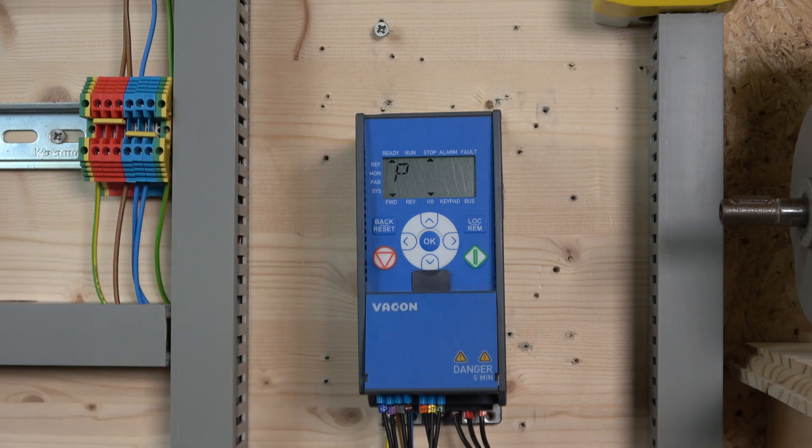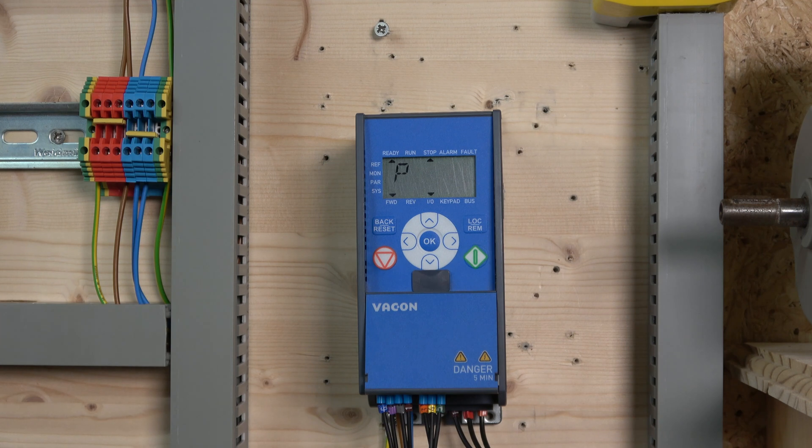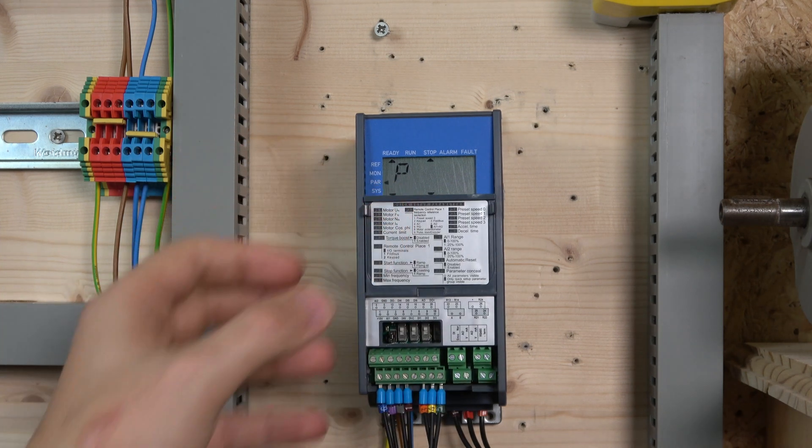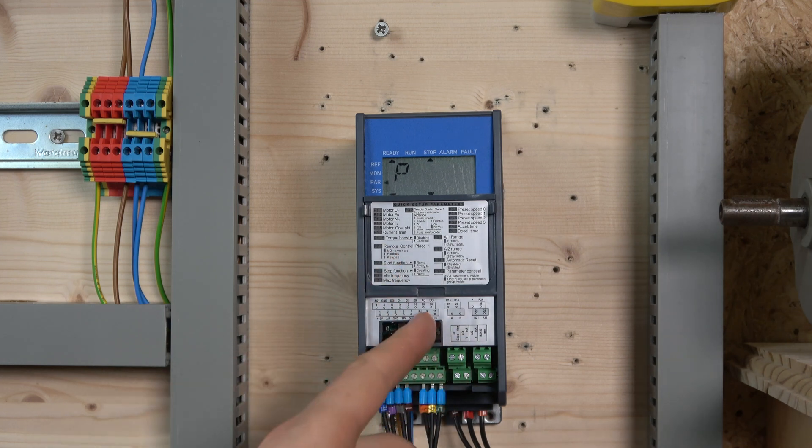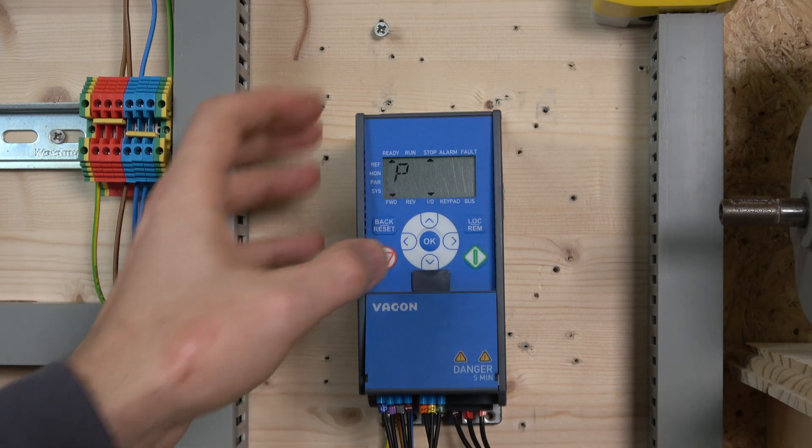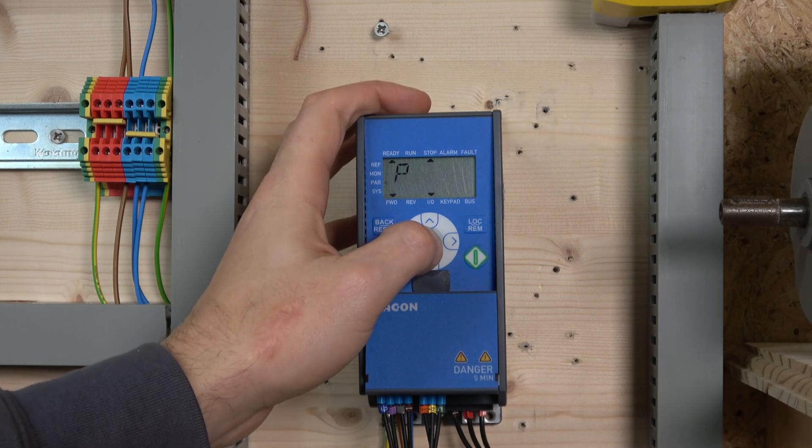For the I/Os, by default the first preset is in parameter P3.1, set to the fourth terminal. If you want to do exactly the same without changing what I'm about to show, just use terminal four - count one, two, three, four. You don't have to change anything. To change the preset frequency, go to parameter 3.5.